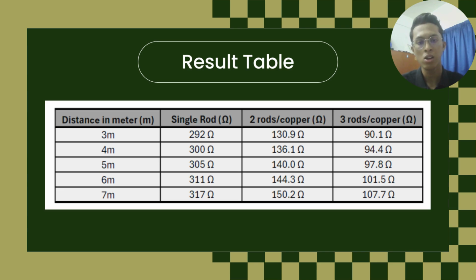The second one is configuration impact. More importantly, as we add more rods to the system, the resistance drops dramatically. By moving from a single rod to a three rod configuration at the 3 meter mark, we see a reduction from 292 ohm all the way down to 90.1 ohm. These numbers provide the raw evidence that the quantity of rods is a much more significant factor in reducing resistance than the specific distance of the installation.